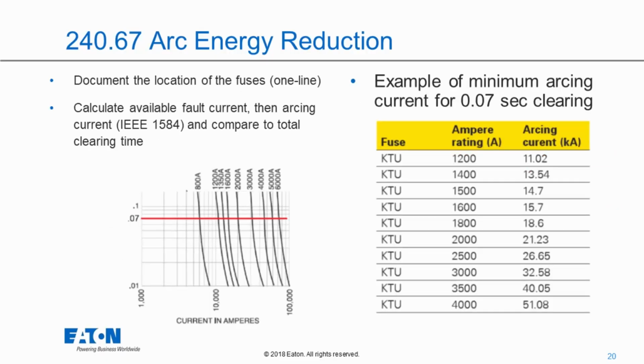So if we look at this, how do we comply? Let's say we do have in our system fuses that are 1,200 amps or higher. We first have to document the location of those. One method to do that would be to identify their location on the one-line diagram of your system. We then have to calculate the available fault current, and there's a variety of different ways you can do that. You can use programs, you can do hand calculations. Bussmann has a mobile app called FC2 that does available fault current calculations.